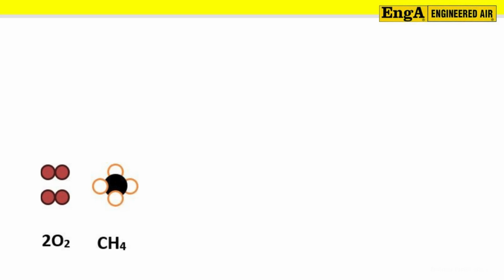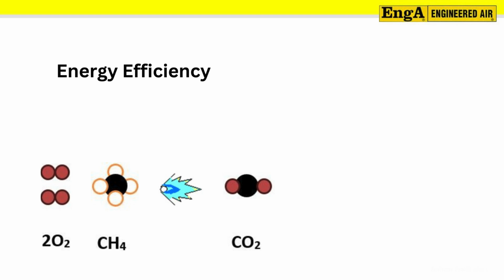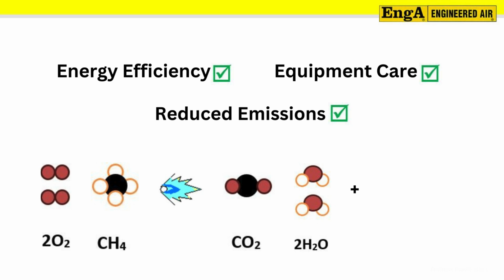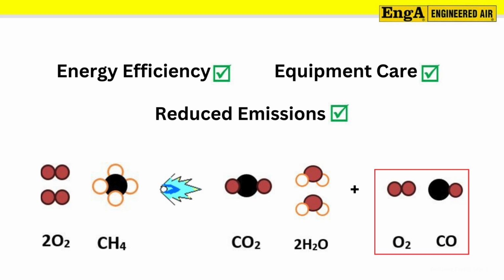Adequate air-to-fuel mixture is important to ensure efficient energy transfer through the heat exchanger, maintain equipment longevity, and reduce the number of pollutants being released into the environment. Two of the main components released are oxygen and carbon monoxide, which a combustion analyzer is designed to measure.